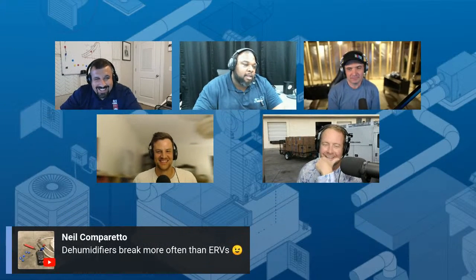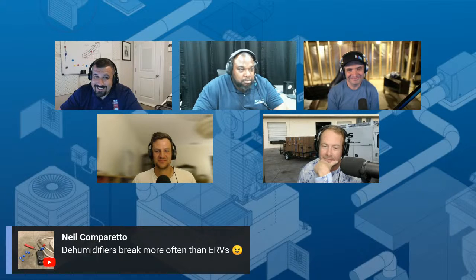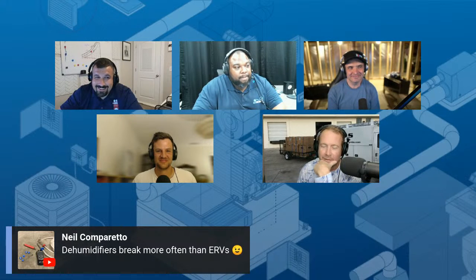We have a couple of Neil Comparetto comments. He says big bad fittings are good, and he's really trying to stir the pot here. Yeah, dehumidifiers. He makes a good case. He does, and it has been a problem. It is. Evap coil failure, especially if you're drawing out of attics with foam that maybe has high TVOCs. We are seeing a lot of evap coil failure.